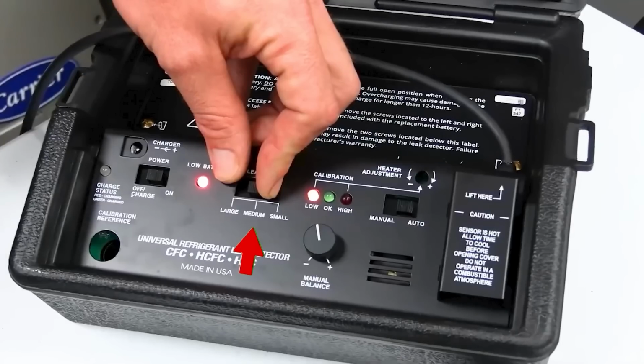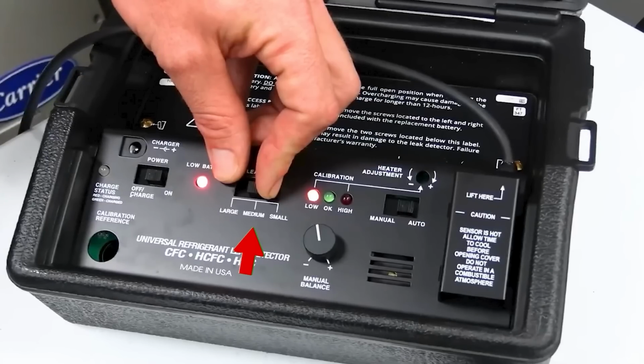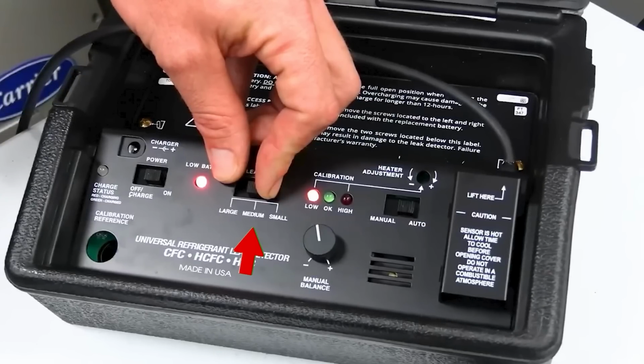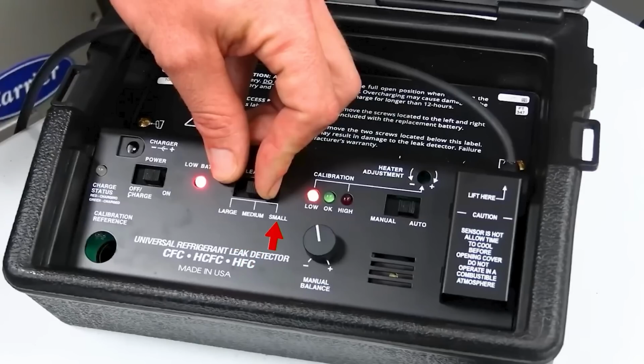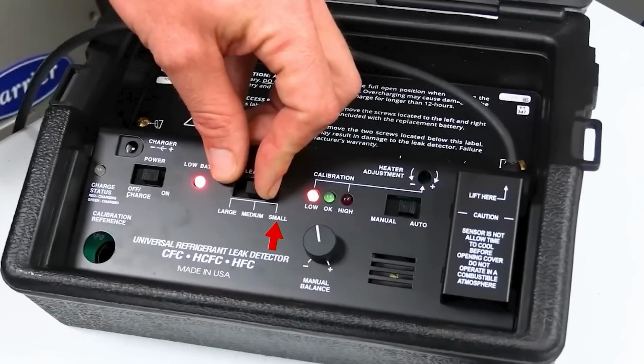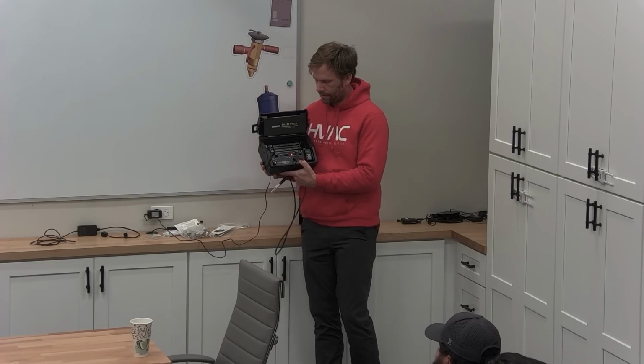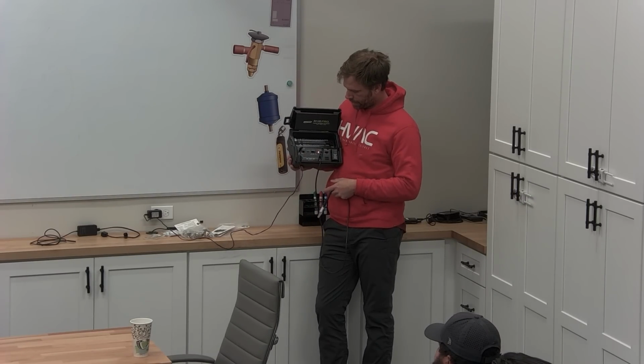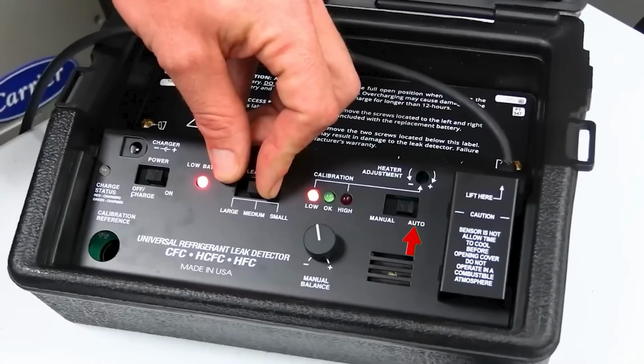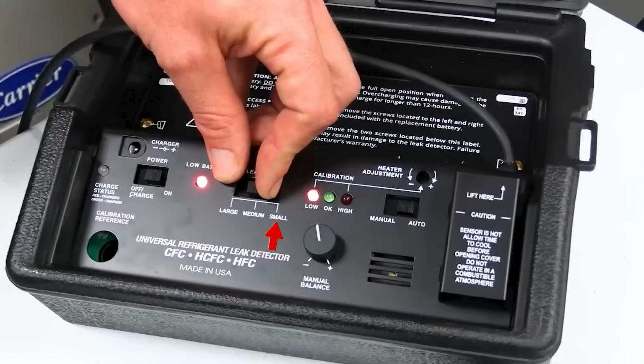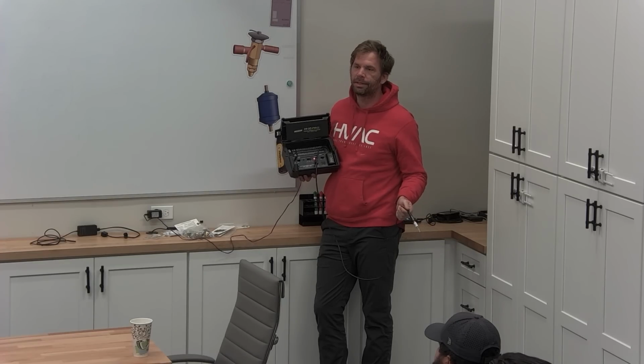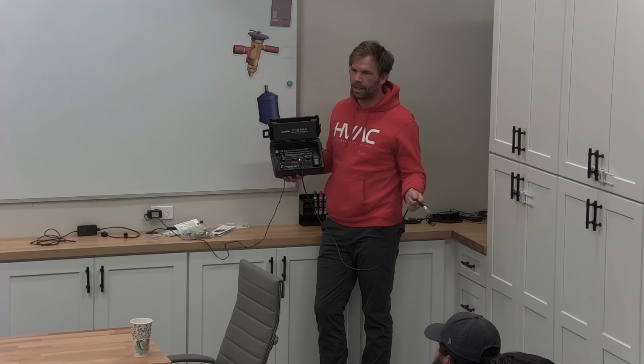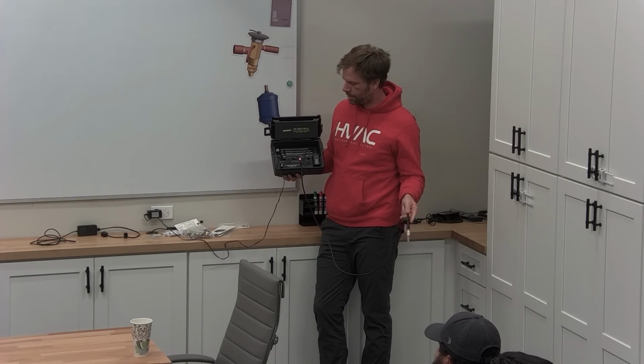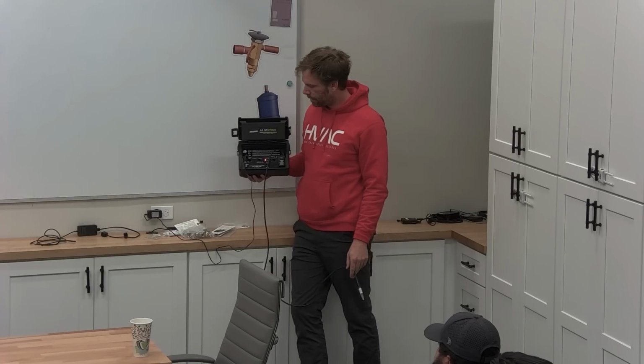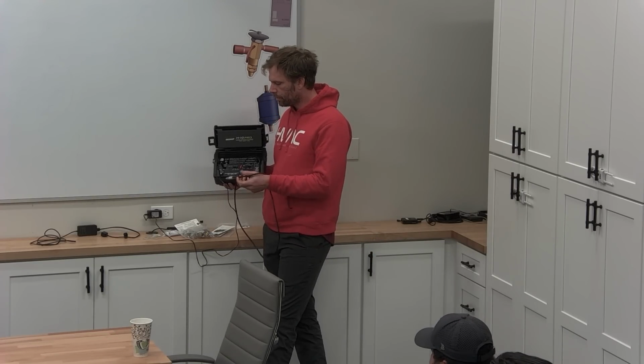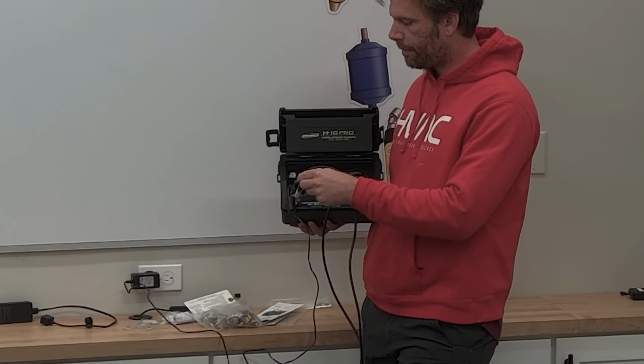Next we have on here our leak sizes: large, medium, small. When you're going to test with the calibrator, it needs to be on small. And so switch it. They suggest in the instructions you put it on auto, you set it to small, and then you let it heat up for 2 minutes before the calibration. And that sensor's nice and hot, and then go across and find it. This one's probably already warm. We're going to find out.